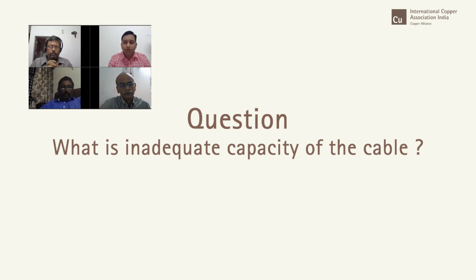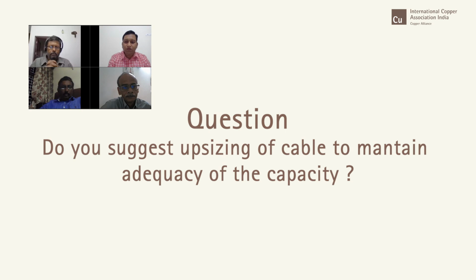Okay, but then do you suggest upsizing of cable in this particular matter to maintain the adequacy of ampacity? See, the main thing is copper cable is expensive, so people try to compromise. Suppose Sivaram Krishnan recommended 6 square mm, and then people go for 4 square mm and things like that, without realizing the consequences of undersized cables. So it is always better to go higher.